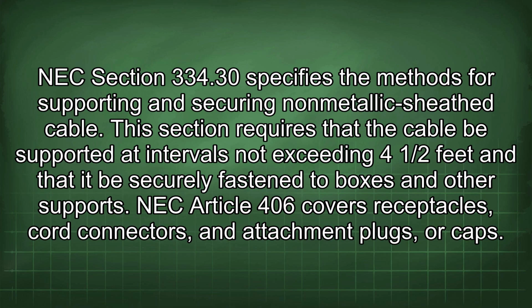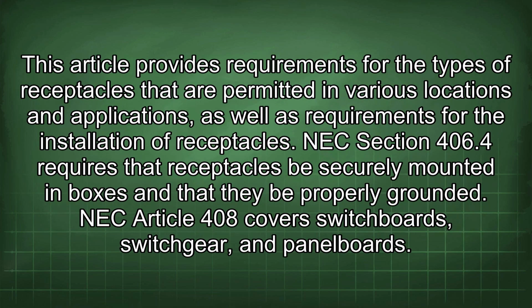NEC Article 406 covers receptacles, cord connectors, and attachment plugs, or caps. This article provides requirements for the types of receptacles that are permitted in various locations and applications, as well as requirements for the installation of receptacles. NEC Section 406.4 requires that receptacles be securely mounted in boxes and that they be properly grounded.